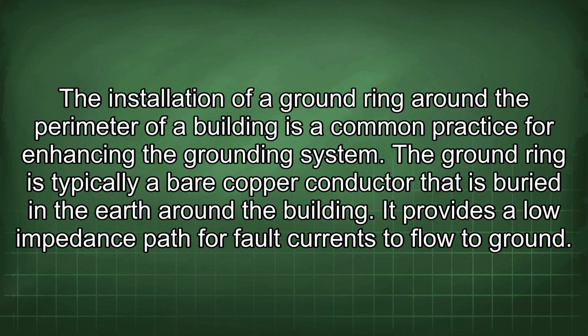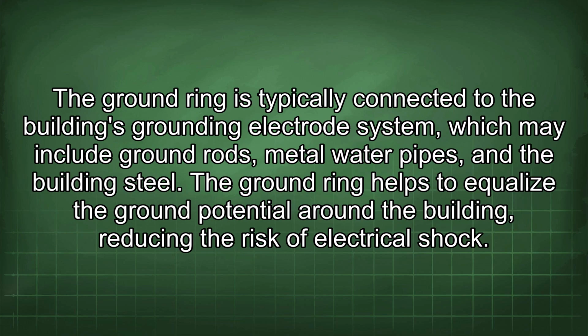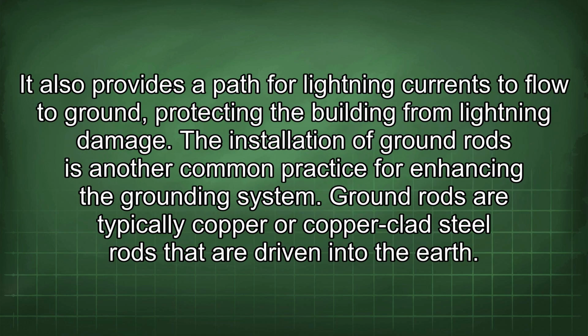The installation of a ground ring around the perimeter of a building is a common practice for enhancing the grounding system. The ground ring is typically a bare copper conductor that is buried in the earth around the building. It provides a low impedance path for fault currents to flow to ground. The ground ring is typically connected to the building's grounding electrode system, which may include ground rods, metal water pipes, and the building steel. The ground ring helps to equalize the ground potential around the building, reducing the risk of electrical shock. It also provides a path for lightning currents to flow to ground, protecting the building from lightning damage.